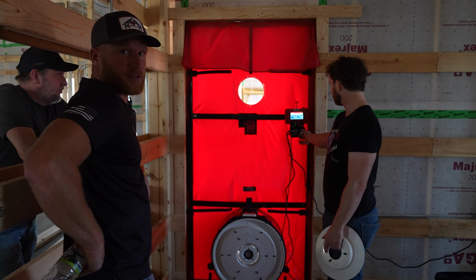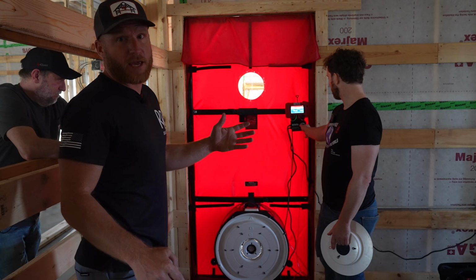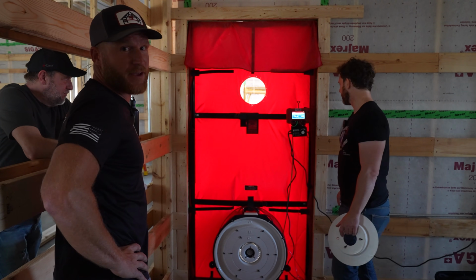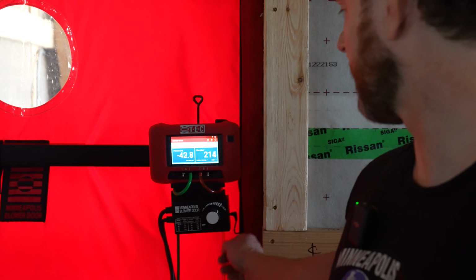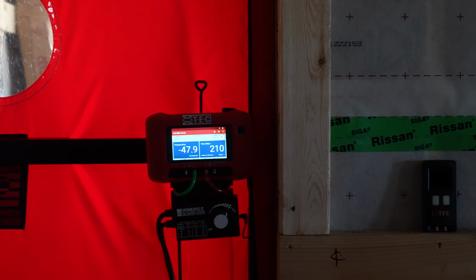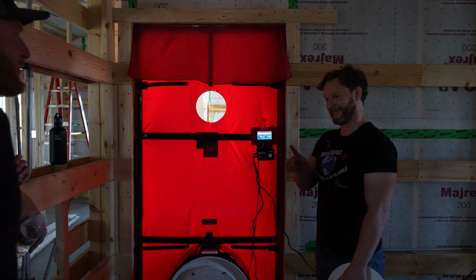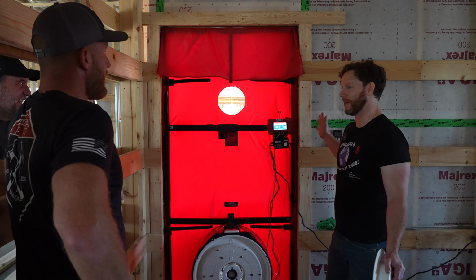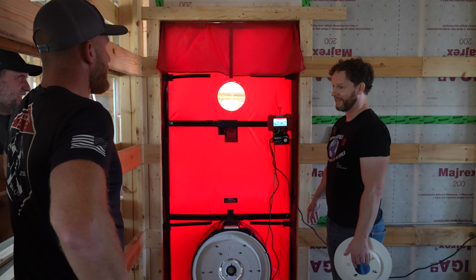Okay, so we made all the fixes, and now Jake put a smaller ring on because ring B is too big of an opening for the air leakage that we had. We had some really dumb mistakes, guys. We totally missed some spots. Oh, we're gonna stay under 300? Oh boy, we're low 2s? Wait for it. So that compressibility of air, I'm not turning that up anymore. So this is just the pressure finally equalizing through your building.